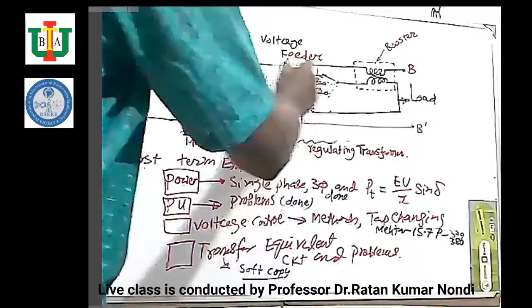The booster's primary is connected with the main transformer. The booster's secondary is connected with the regulating transformer. So, if the voltage is required to increase, then the booster secondary voltage will be added. Sometimes it will be subtracted. Phase sequence and polarity are there. Polarity means additive polarity or subtractive polarity. I am showing you about polarity, you see.